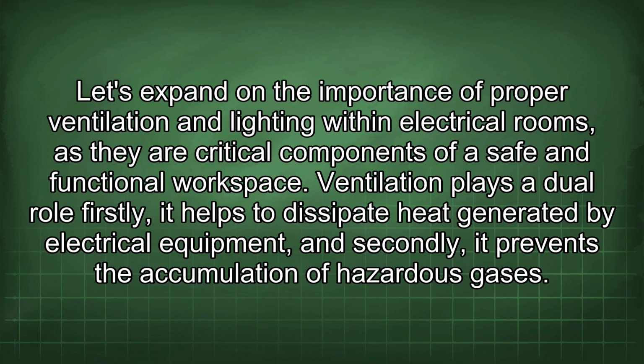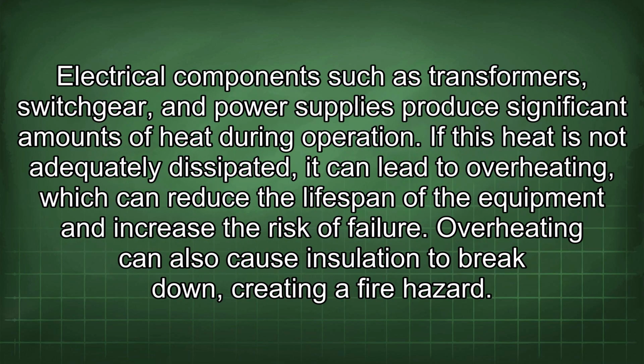Let's expand on the importance of proper ventilation and lighting within electrical rooms, as they are critical components of a safe and functional workspace. Ventilation plays a dual role. Firstly, it helps to dissipate heat generated by electrical equipment, and secondly, it prevents the accumulation of hazardous gases. Electrical components such as transformers, switchgear, and power supplies produce significant amounts of heat during operation. If this heat is not adequately dissipated, it can lead to overheating, which can reduce the lifespan of the equipment and increase the risk of failure.